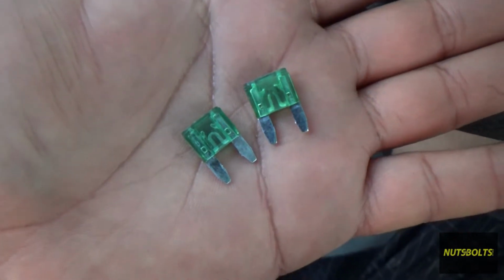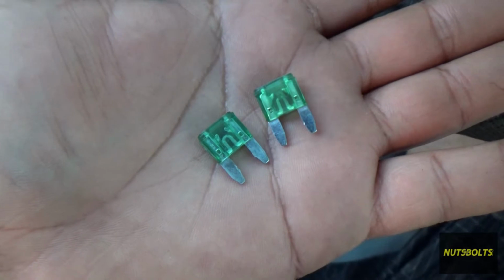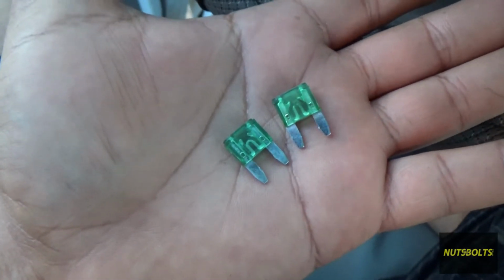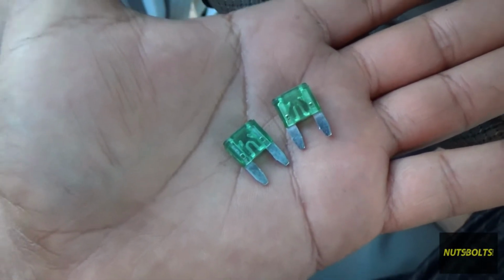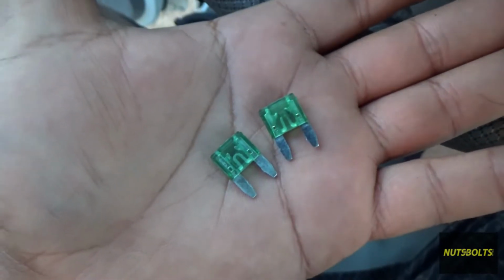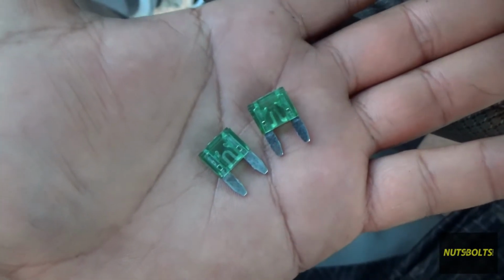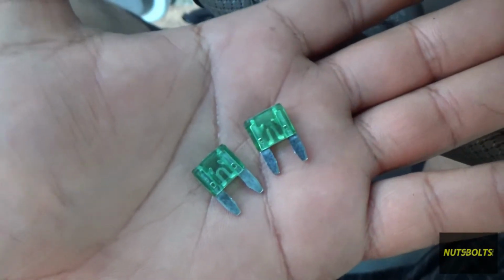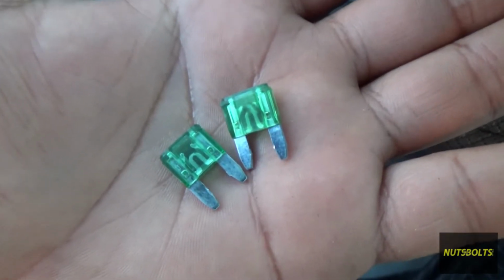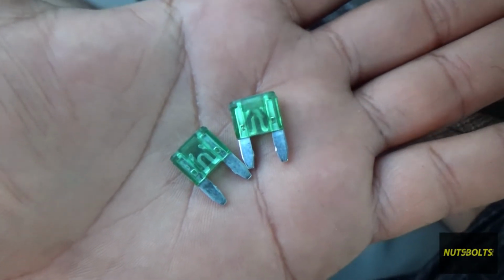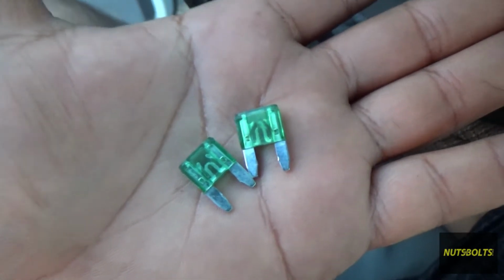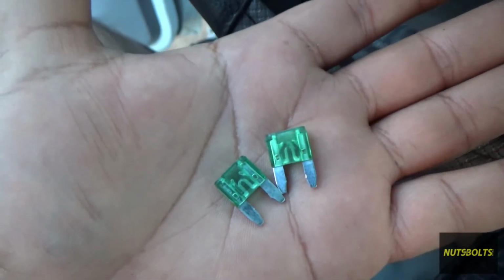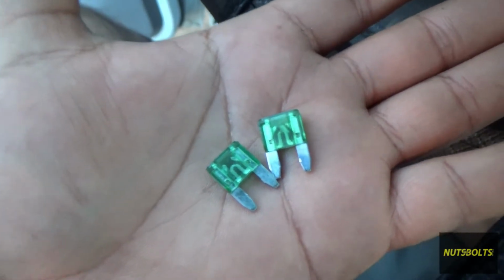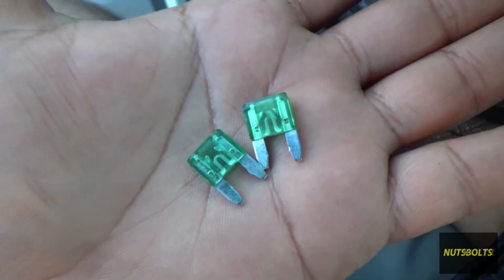One final thing: when replacing a fuse, always install one rated to the same capacity as the original. Fuses are chosen to protect the circuit and are meant to be the weakest link—they're supposed to blow before the wiring, the component, the motor, or anything else. Installing a bigger fuse makes the wiring or a light bulb the weakest link instead, which could cause a fire.